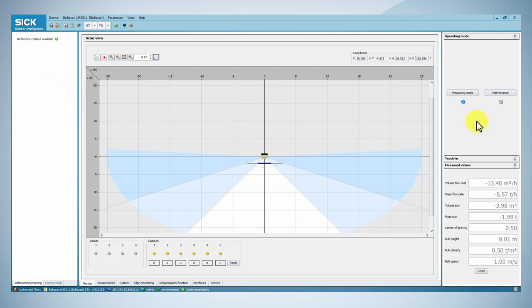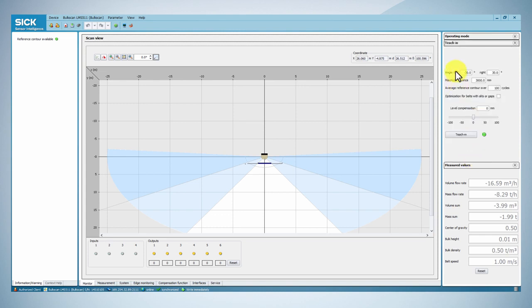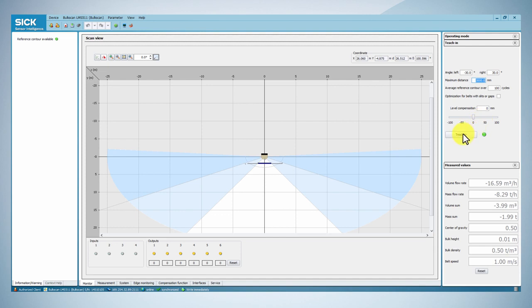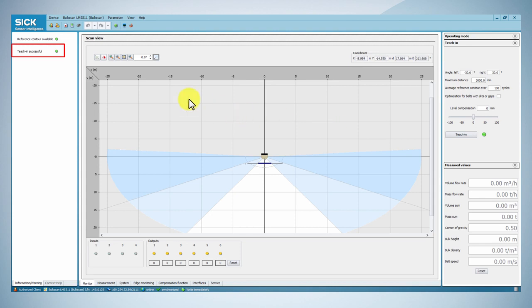We will start the commissioning by teaching the reference contour. Set the left and right angles such that the maximum possible conveyor belt width can be acquired. Consequently, set the maximum distance and then click on the teaching button. As soon as the teaching is finished, the green indication appears in the top left box.